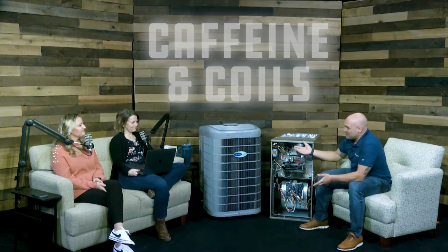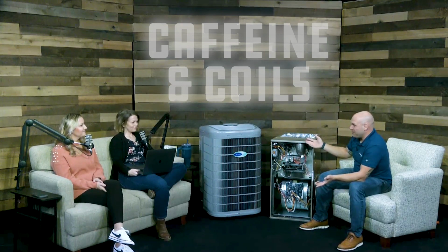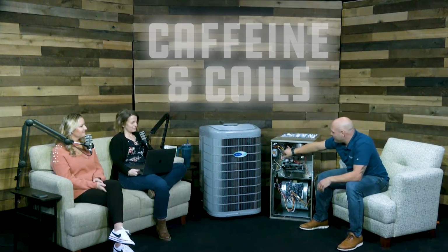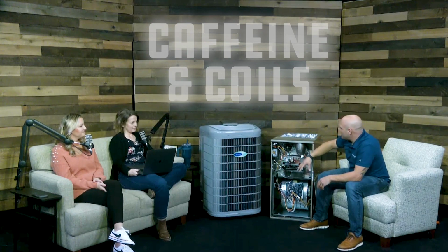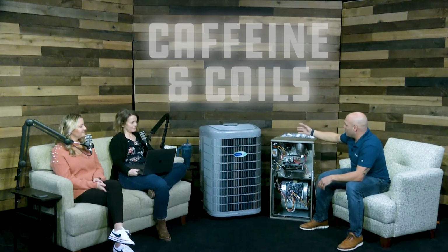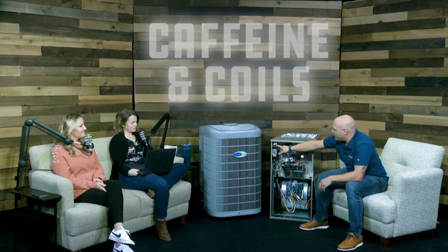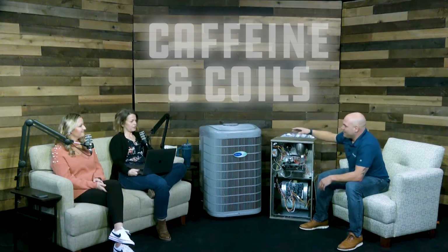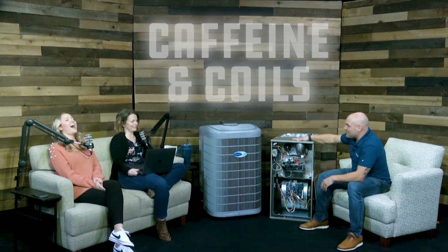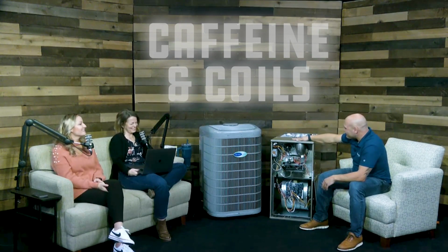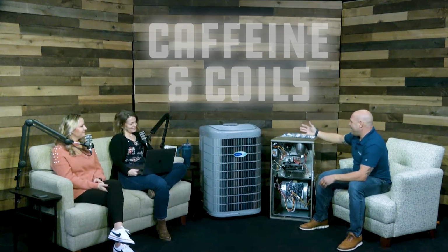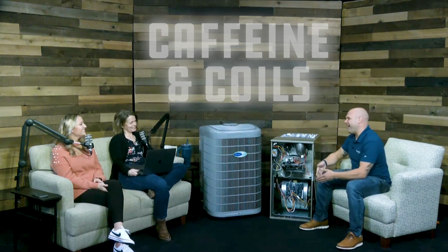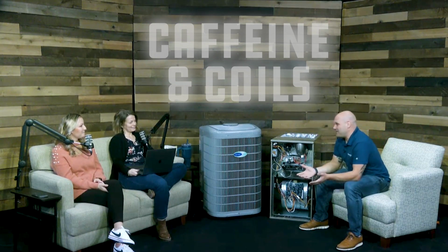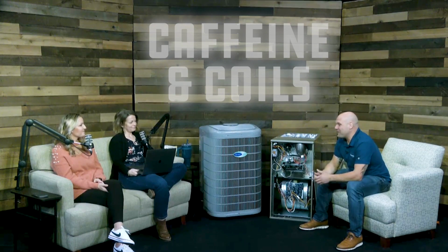Yeah, but it's actually part of your code 33, your error code, being the pressure switch. Your draft inducer motor could be working just fine, but if it's not blowing enough air through your flue vent, then you're not going to pull the switch in. So code 33 could be a deceased bird in your flue vent. Oh my goodness. I don't have a specific time, because it's happened to me more than once. But I think the first time I pulled a bird out of a flue vent was definitely funny. Oh my gosh.